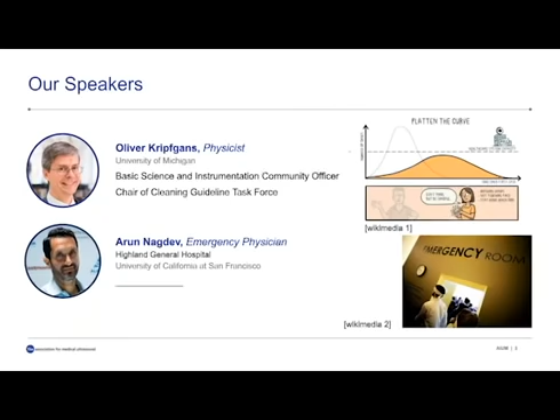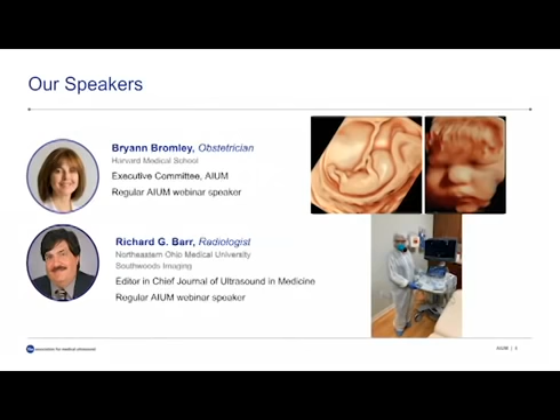As I said, I'm Oliver Kripfgans. I'm a physicist. I'm the chair of the Cleaning Guidelines Task Force at the AIUM, and I will be presenting information from the literature. So the AIUM guidelines for cleaning and preparation are mostly concerned with cleaning of transducers and equipment. As you know from a previous documentation from the AIUM, the transducers are categorized into external transducers, interventional, transcutaneous or percutaneous transducers, internal transducers, etc. The equipment is concerned with keyboards and handles on the ultrasound machines, but also with gel bottles. For cleaning to be effective, it is very important to not only disseminate educational materials, but to also understand the materials and execute them, and then finally also document them.